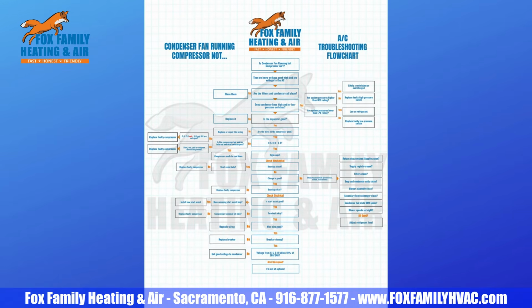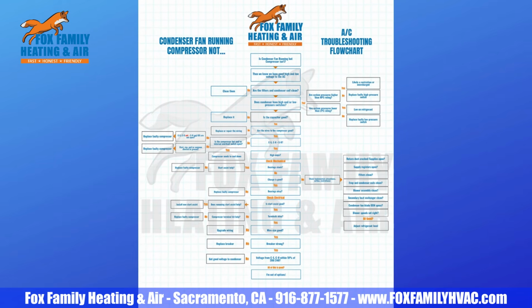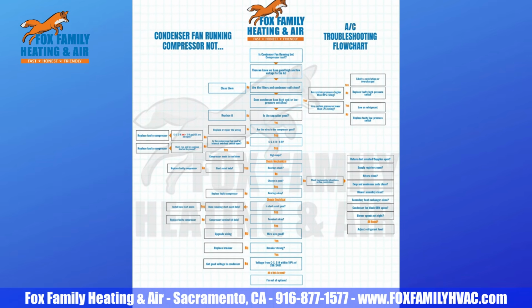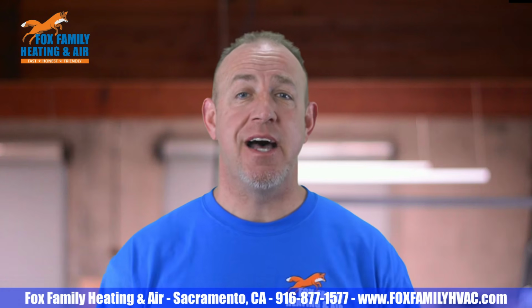By running through this flow chart, you will be able to successfully diagnose why the fan on the outdoor condenser might be running, but the compressor is not.